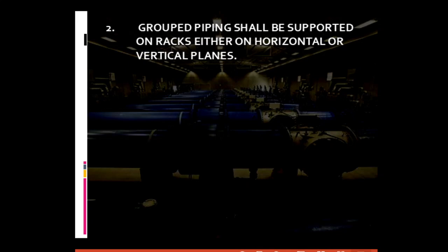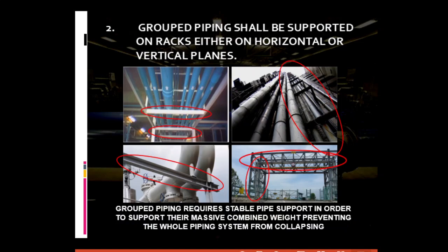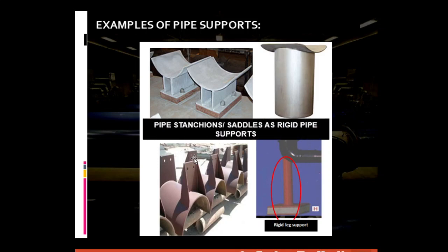For general piping requirement number two: group piping should be supported on racks either on the horizontal or vertical planes. A span of piping is heavy and is heavier when fluids pass along the pipe. Group piping results in enormous weight that, if not properly supported, would cause the entire piping system to collapse. In the picture, we can see different kinds of pipe supports, including a pipe stanchion — similar to a horse saddle — which are examples of rigid pipe supports. The lower picture shows a fabricated rigid leg support.